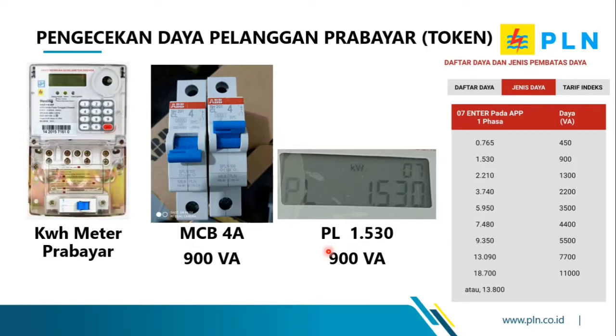Untuk mengetahui daya pelanggan di KWH meter prabayar atau KWH meter token, sama seperti halnya pada pelanggan pasca bayar — kita dapat memperhatikan MCB yang terpasang. Contohnya, jika terpasang MCB 4 ampere, berarti daya kontrak pelanggan tersebut adalah 900 VA. Namun ada informasi khusus: kita bisa melakukan pengecekan daya pada KWH meter prabayar walaupun MCB tidak terpasang, yaitu dengan cara menekan kode 07 enter pada KWH meter prabayar tersebut.